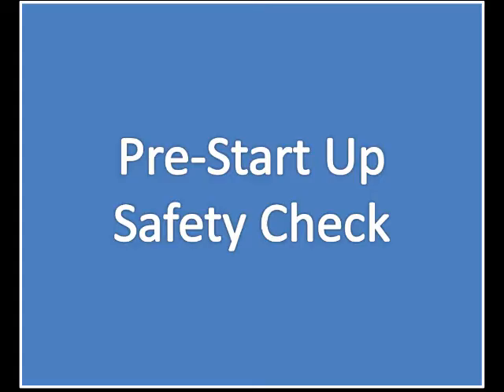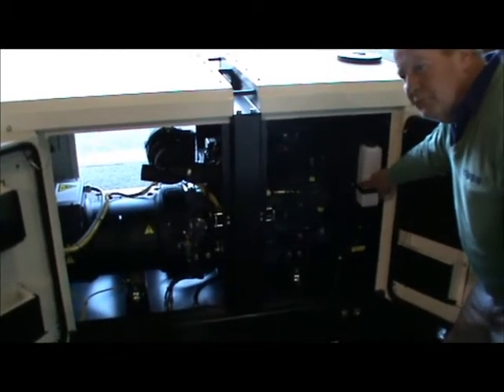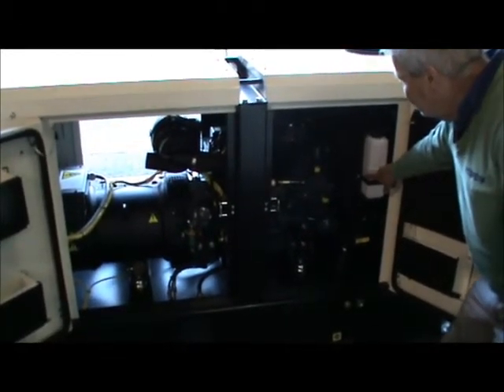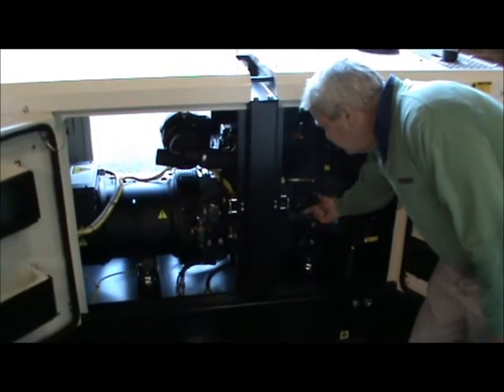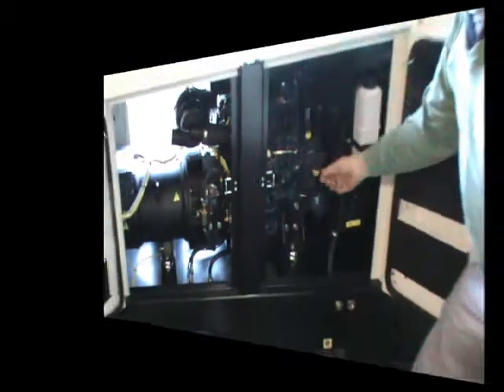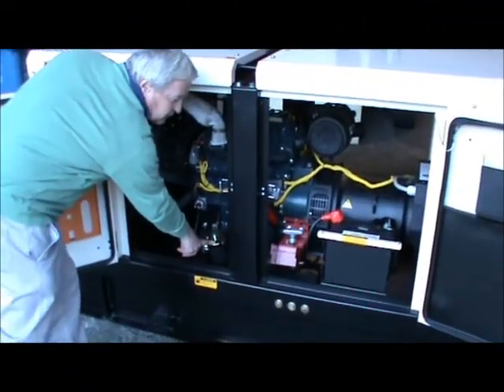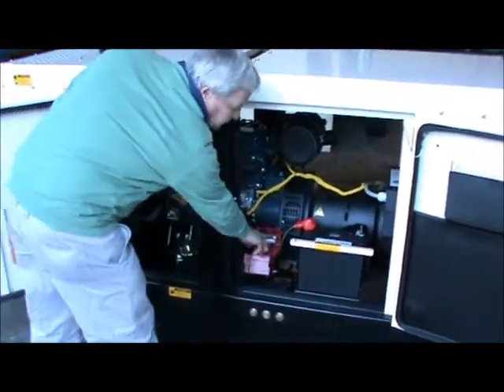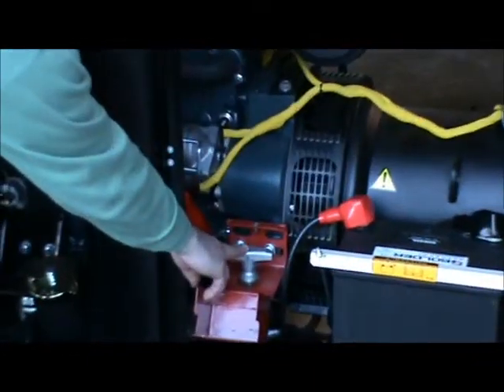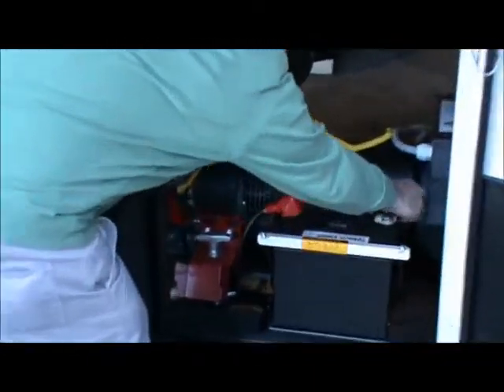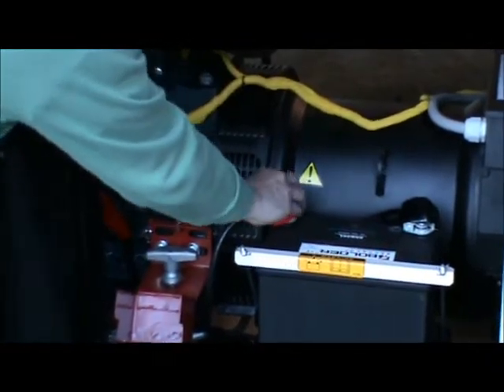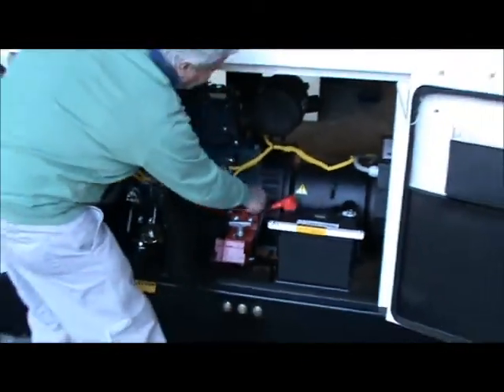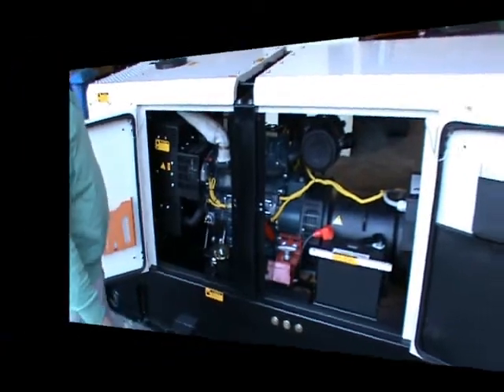Before starting the generator, it is absolutely necessary to perform a pre-startup safety check. First, you need to check all the fluid levels such as coolant, oil, and other lubricants. Make sure all fluid level requirements are reached before you start the machine. On the other side of the machine, you should check the fuel level, making sure the fuel cap is locked in place. Most importantly, you need to check the battery isolator and battery terminals are free of rust and fluid around the spark plugs, as well as any possibility of leaking fluids from the battery.